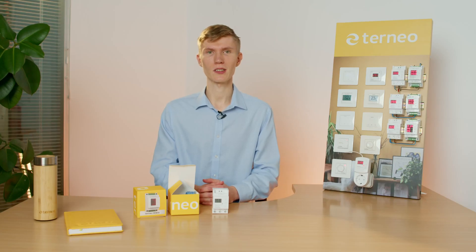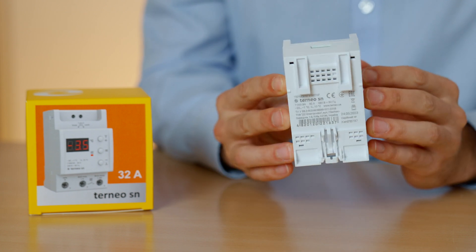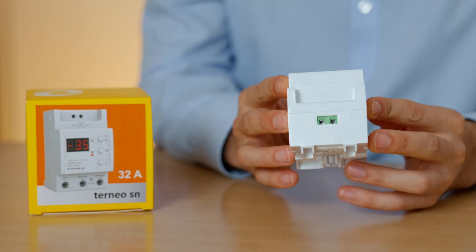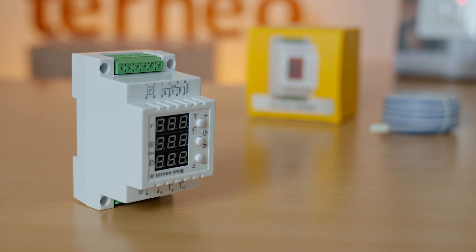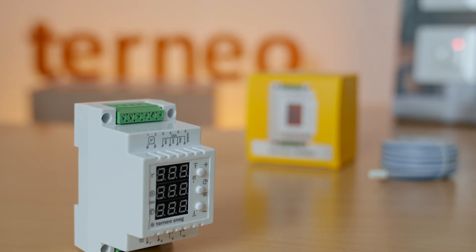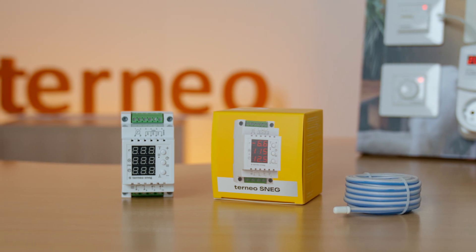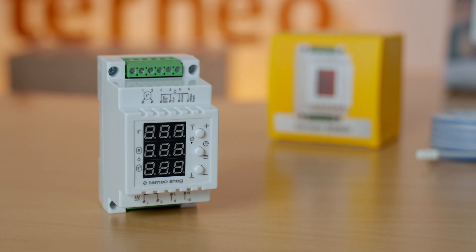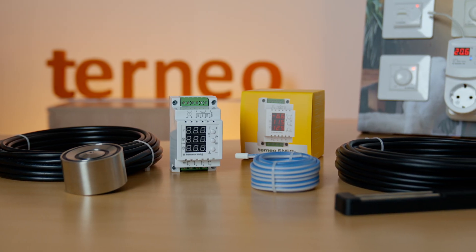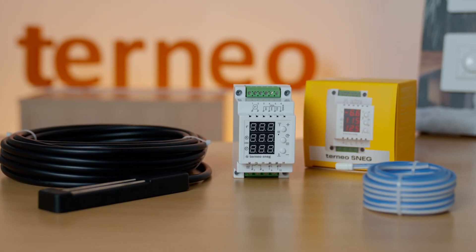Lastly, the fourth group of thermostats: snow melting ones. Here we have the terneo sn. It's controlled by a temperature sensor and switches the heating system on when the outside temperature is in the range of plus 5 to minus 10 degrees Celsius. Our main model also includes a moisture sensor in addition to the temperature sensor. That allows the thermostat to switch the system on only after confirming there is in fact snow outside – it won't activate if it's cold but there is no snow. The thermostat is bundled with either an OSA sensor, designed for pavements or open areas and installed in the ground, or a wall sensor, made for roofs and installed in a gutter.